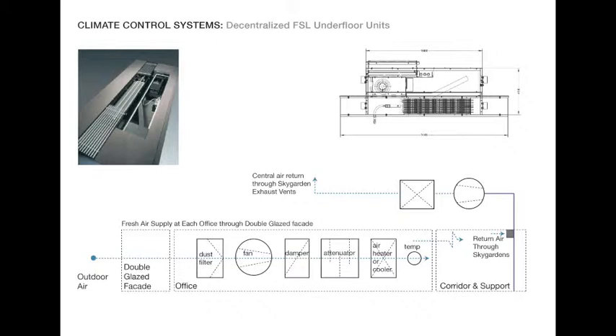The base heating and cooling load is met by the radiant floors. The variable load, i.e. the flux in temperature that occurs at the skin, is met by the fan coil units or the FSL underfloor units. There are 2,000 individual FSL fan coil units in the post tower, supplying decentralized air to each office. Each unit has a conventional convector that allows fresh air to pass through from the double skin facade. The air is then conditioned and supplied to the offices.